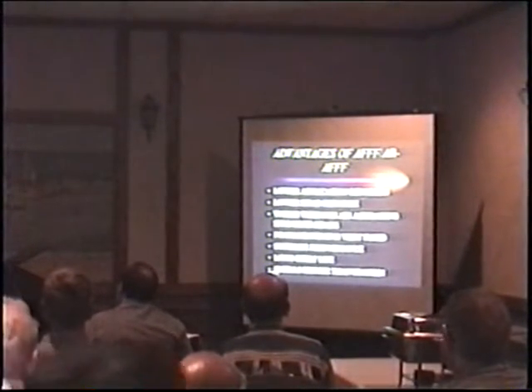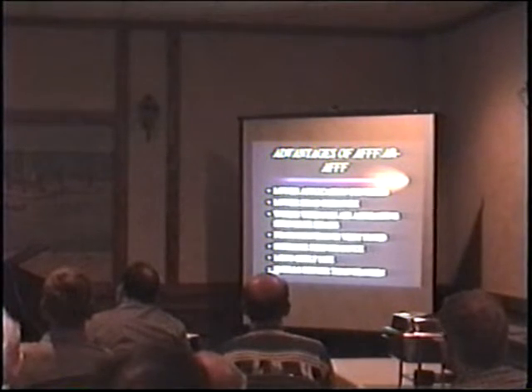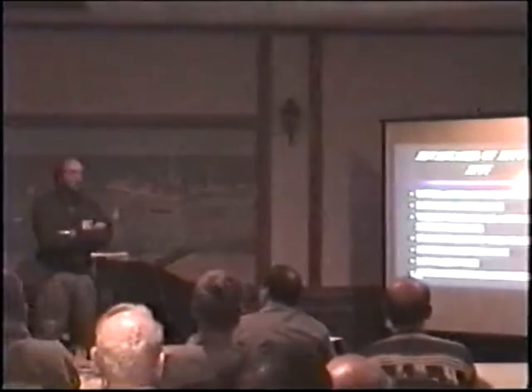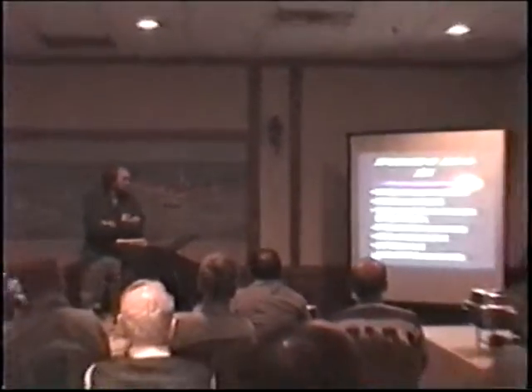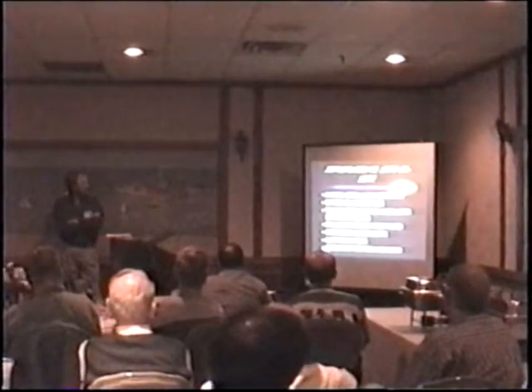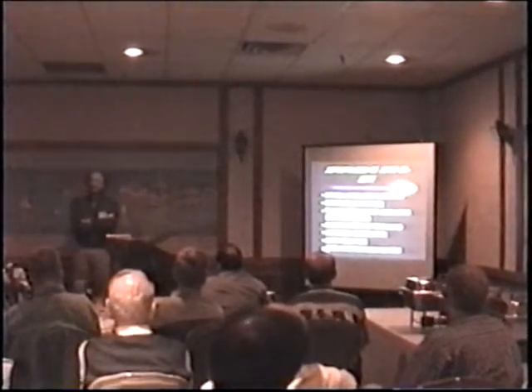Advantages of AFFF are obviously lower application densities. Typical sprinkler application, you're looking at about 0.16. This obviously leads to lower head pressures, which reduces the amount of water you have to have and reduces your pipe sizing. You can use AFFF with non-aspirated sprinkler heads. Again, it'll reduce cost.